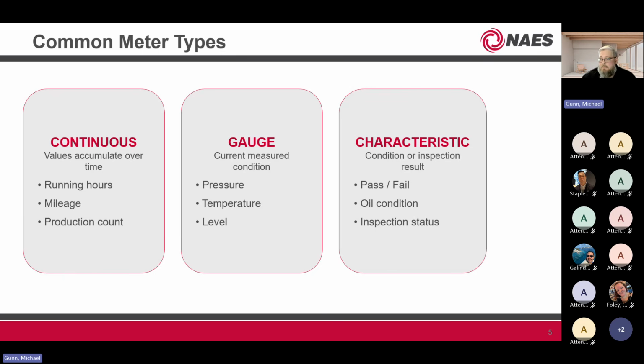The example I always give is the differential pressure on a filter. Once it gets too high, we can use Maximo to trigger a work order saying your differential pressure is too high and you need to replace these filters.